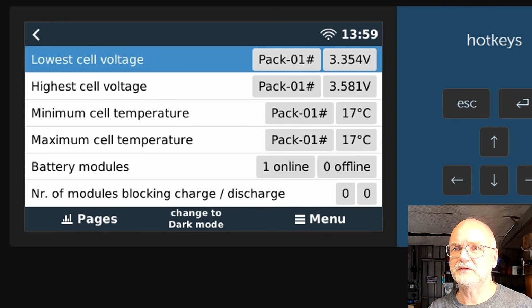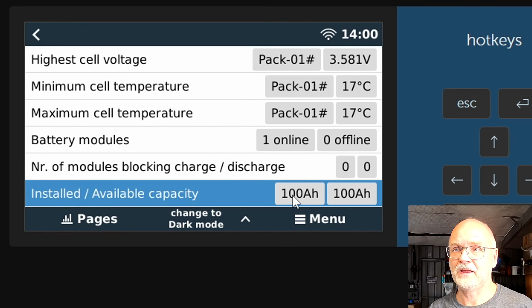Let's have a quick look at the Smart BMS in the Victron remote console. We've got one battery online, showing the highest and lowest cell voltage and temperature. Further down it tells us 100 ampere hours of 100 ampere hours are available. This is not the state of charge - it won't show 77% if the battery is at 77%. It only shows what is available right now if the battery is online. If you have 5 batteries connected and one is offline due to overvoltage protection, for example, it will show 500 installed, but only 400 available at the moment.